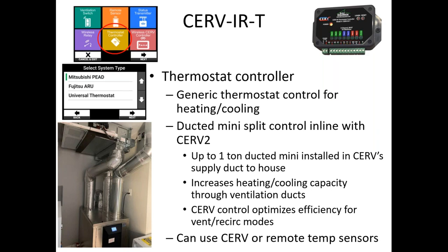So you can do up to a 1-ton ducted mini split installed in line with the CERV. This increases the heating or cooling capacity through the ventilation ducts. And then that CERV control will optimize for efficiency both in ventilation versus recirculation modes. So we can stage the heating or cooling of both the CERV and the mini split to optimize that. And then you can also use those remote temperature sensors, or the built-in temperature reading from the CERV can be linked to this controller to optimize where you'd want to control the temperature from.